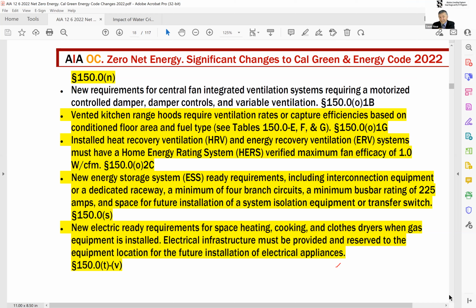But it simply says, if you put that in there, I want all these controls. I want control dampers there. I want them to be controlled, motorized, with variable ventilation. So you just can't have a constant volume. The time that I did, I had a constant volume. Now, if you have a kitchen range hood, you must follow that. It's very simple. It simply says depending on the conditioned area, the vented kitchen range hood will be there, and they give you the duct size, and it also relates to whether the fuel is gas or electric. That makes a difference.